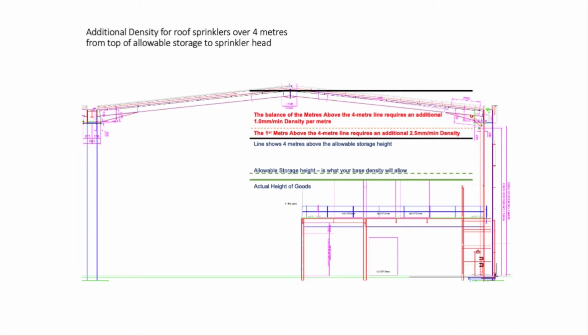Four metres from that you should have sprinkler protection. However, in this case we've got a bit more - so for that first metre above the 4 metres, you'd add another 2.5 millimetres of density, and above that, for whatever the meterage is, say 5 metres, you'd add 5 millimetres of density. So it's 1 millimetre of density per metre after that.